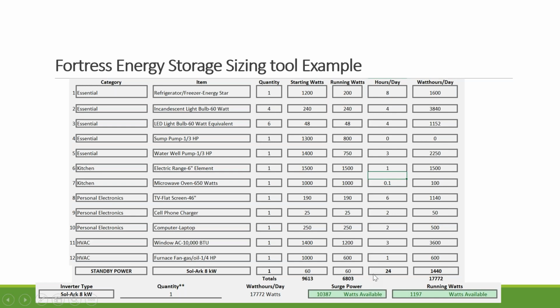So this particular house needs about 9,600 watts starting wattage, right? Again, this assumes everything turns on at the same time. Could that happen? Yes, but the likelihood is very low. And then the running wattage, when you have everything on, needs 6,800 watts, 6.8 kilowatts. Total consumption is close to 18 kilowatt hours. Now with the Sol-Ark 8kW inverter, in this case, the customer chose to go with the Sol-Ark 8kW.